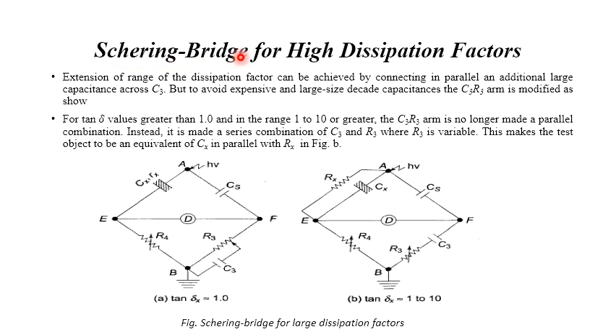Next concept is the Schering bridge for high dissipation factors. The extension of the range of the dissipation factor can be achieved by connecting in parallel an additional large capacitance C3. So this is what we have: the known value, the standard, and R4, C3, and R3. But to avoid expensive and large decade capacitances, the C3 R3 arm is modified, as you can see here.